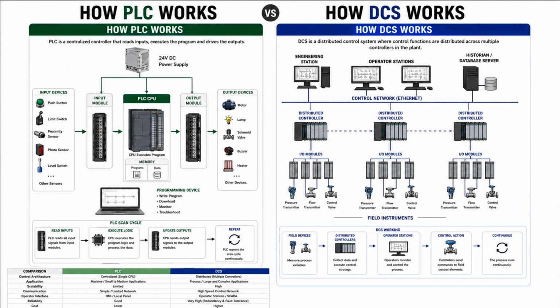Real industrial example. Imagine a bottling machine producing soft drinks. It has sensors, motors, and pneumatic cylinders. One PLC can easily control everything. Now imagine an oil refinery. Thousands of pressure transmitters, flow transmitters, temperature transmitters, control valves, compressors, boilers, heat exchangers, and safety systems. No single PLC should manage all of that. A DCS is designed exactly for this level of complexity.